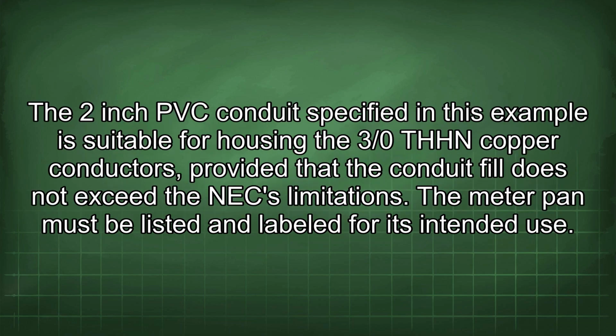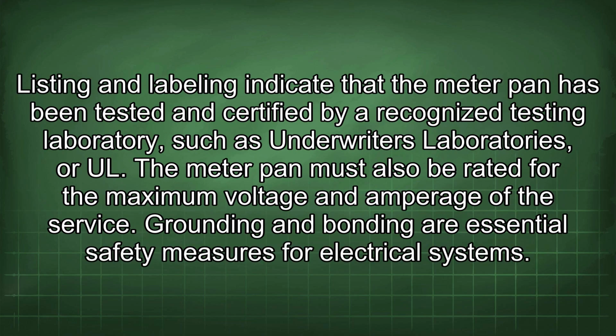The 2-inch PVC conduit specified in this example is suitable for housing the 3/0 THHN copper conductors, provided that the conduit fill does not exceed the NEC limitations. The meter pan must be listed and labeled for its intended use. Listing and labeling indicate that the meter pan has been tested and certified by a recognized testing laboratory such as Underwriters Laboratories, or UL. The meter pan must also be rated for the maximum voltage and amperage of the service.